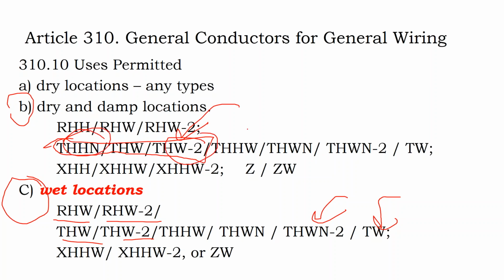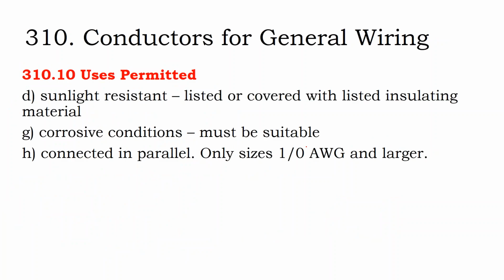So the letters do have some correlation. Like this -2 is for more harsh environmental conditions. So when you're doing a solar cable, you really want to be using this W, be looking for this W-2, and usually that indicates a good solar cable. What the cables actually are, there are charts in section 300 and 310 that line them out to you. So there are cables listed for sunlight resistance, for corrosive conditions. You're only allowed to parallel cable that is size 1/0 and larger.